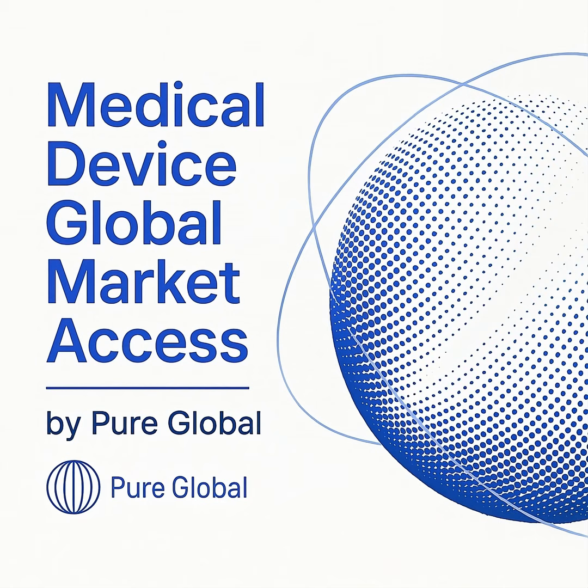First, let's clarify what we mean by unclassified devices. These are not new, high-risk devices. Rather, they are products that were legally on the market before the medical device amendments were passed in 1976. When these amendments were enacted, the FDA began the massive task of classifying all existing devices into Class 1, 2, or 3 based on risk. However, a small subset of these pre-amendment devices were never formally assigned a class. They have existed in a state of regulatory limbo, generally requiring a 510(k) submission by default, just like most Class 2 devices, to demonstrate substantial equivalence to a predicate device.